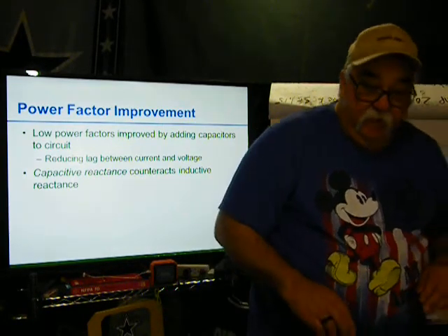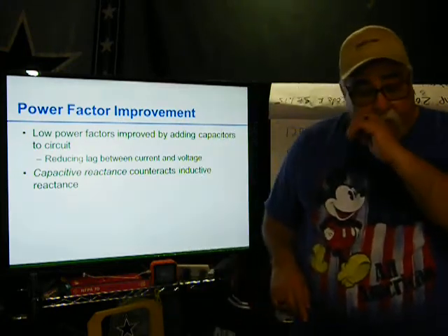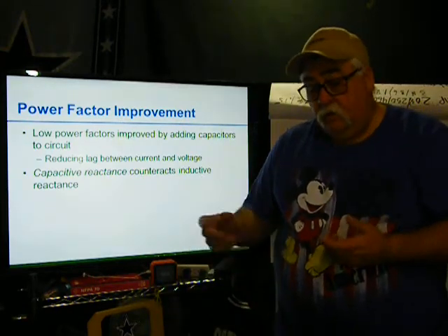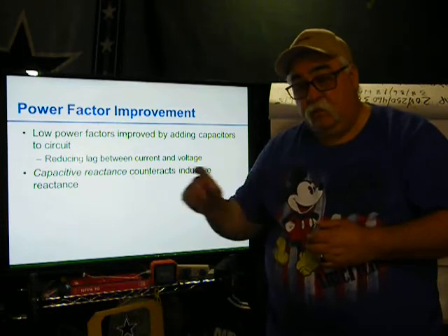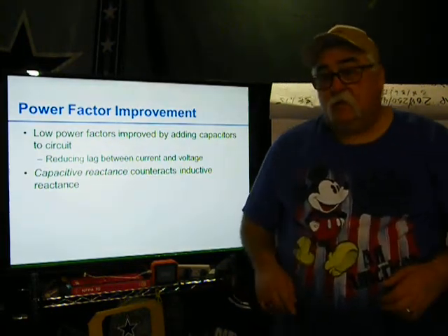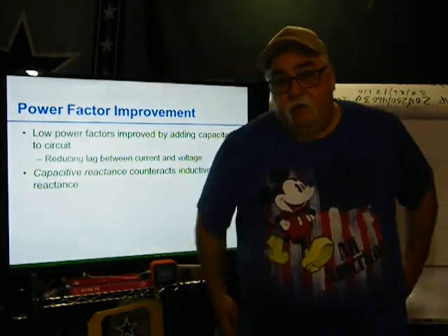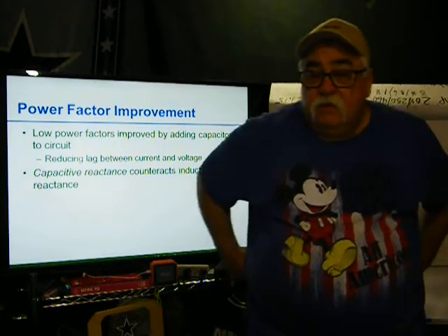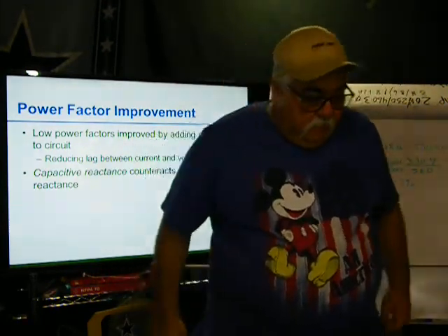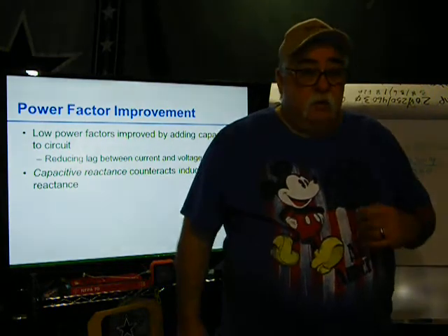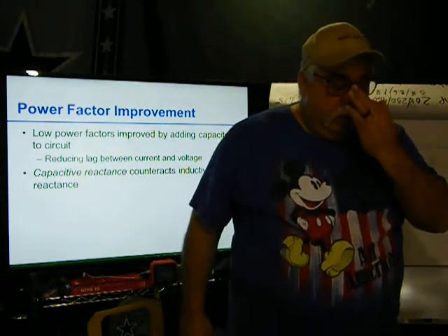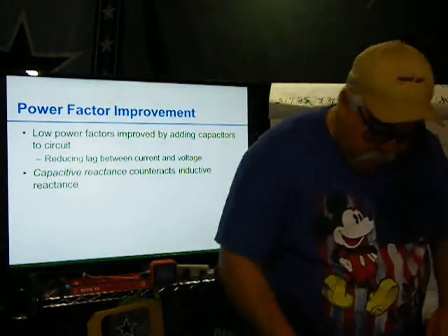A lot of times you can find the power factor on a motor, and you look at the motor and it says 0.86 or it says 86.6%. That's that cosine. Okay, so that power factor is already low. Motors aren't 100% efficient. Some already come with a capacitor on it too. Clean that up a bit, and some don't.